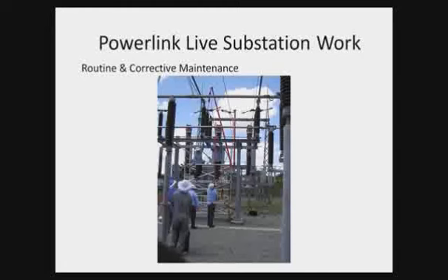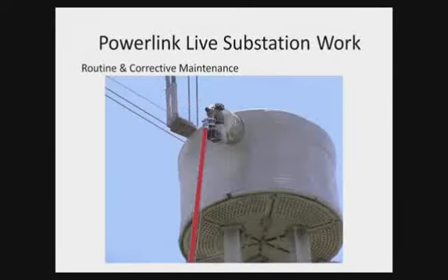A little harder to see in this case, where we've lifted the whole insulator column and arms down using what you see there, a big hot stick boom, effectively becoming a little crane for lifting items down. There wasn't enough room to get operators up bare hand between phases, so we had to work hot stick and bring the equipment down.